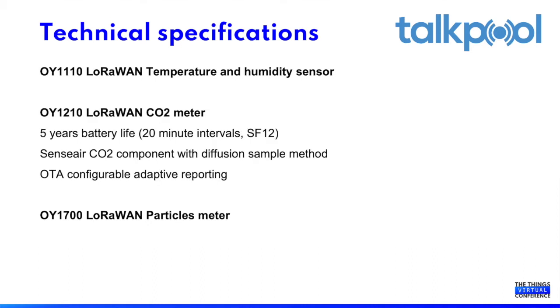The carbon dioxide sensor, the 1210, has a 5-year battery life, measuring every minute and reporting the value every 20 minutes. One unique feature is that when the carbon dioxide level changes more than a configurable value, typically 100 ppm, you get automatic additional measurements in between. That is really good for HVAC optimization. For example, if you have a conference room and a lot of people coming into the room, the sensor measures that directly and sends extra measurement reports.